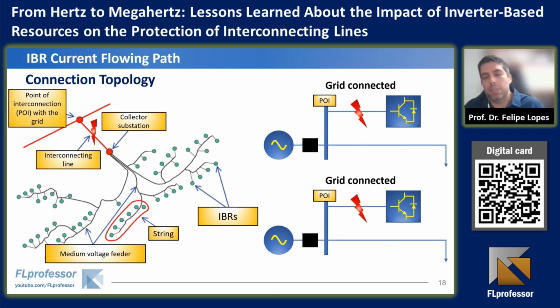The same is verified when we consider an internal fault. In this case, there is a contribution which comes from the grid, and another contribution which comes from the IBR. So if we consider the current measurements from both sides, if we are talking about grid following technologies, the problems may appear at one side, but they may not be observed on the grid side. And this behavior can be expanded to understand some behaviors related to modern technologies, such as the traveling wave-based technologies.